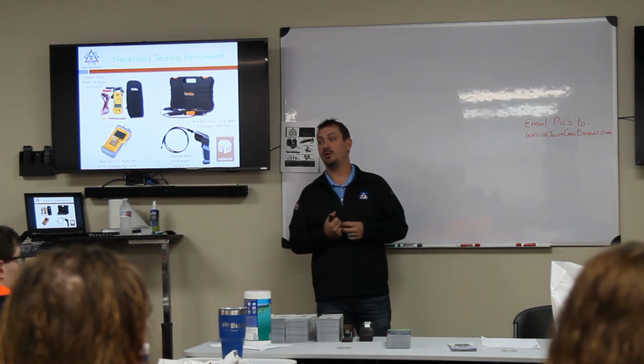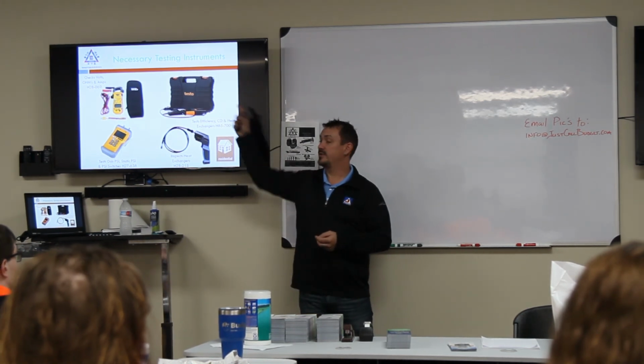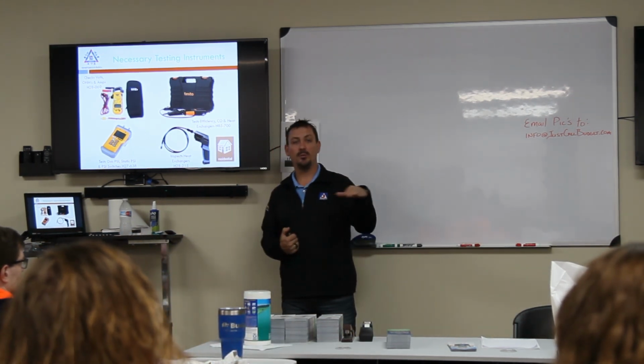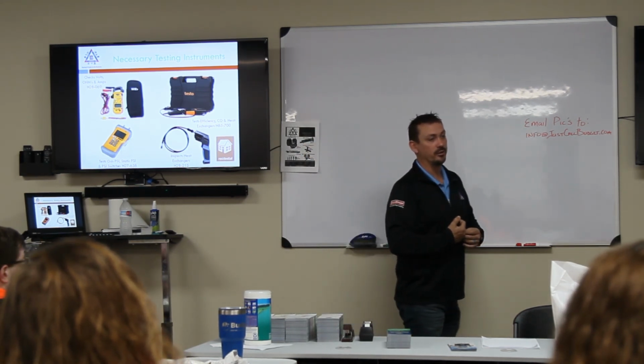So having a personal CO detector on you at all times, in my opinion, is one of the safest things we can do in our industry to help protect ourselves. But this also can be walked around and used as a CO detector inside homes. And then you can also potentially look for cracked heat exchangers. Right now we're at 21% oxygen inside this room. It's actually 20.9%, what we call 21%. We stick that into a flue.